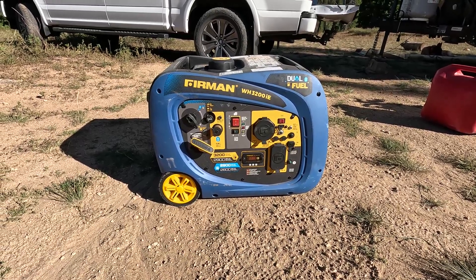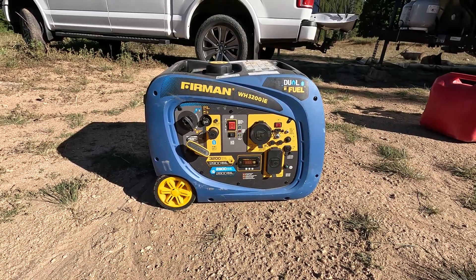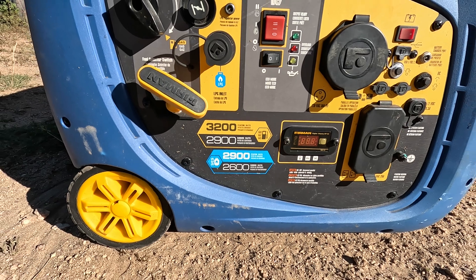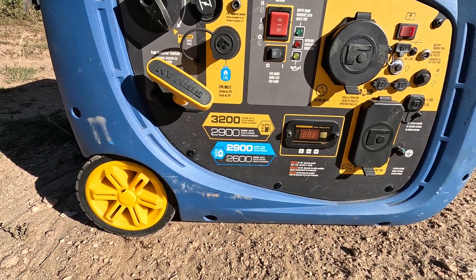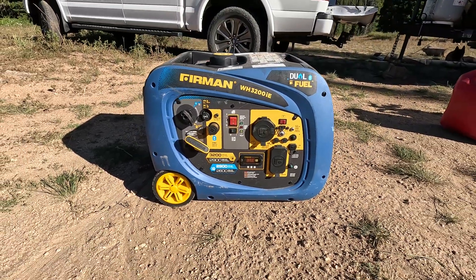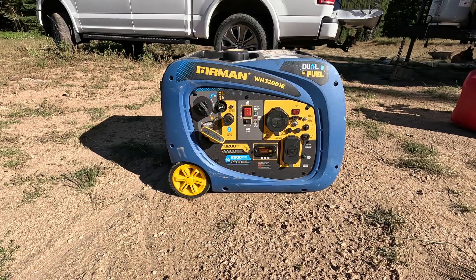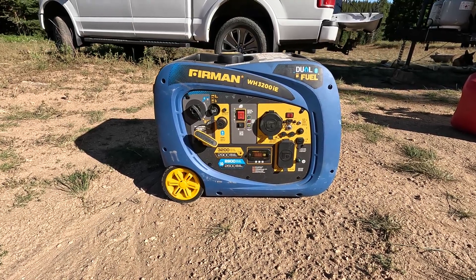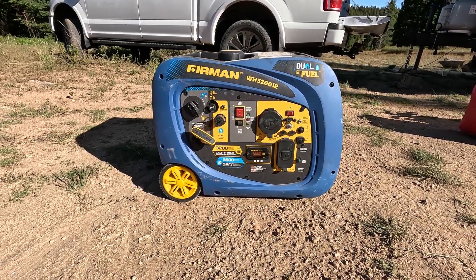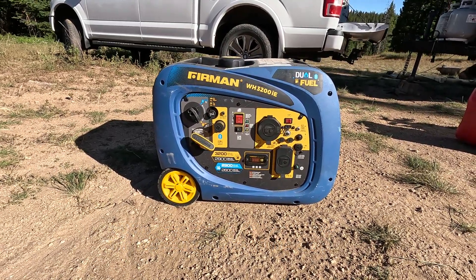I have this FIRMAN WH3200iE dual fuel inverter generator. At sea level, this generator is rated at 3,200 watts surge on gasoline, 2,900 watts running on gasoline, and then 2,900 watts surge and 2,600 on propane. We're going to do tests here today at 10,000 feet. Generators normally lose 4% of their rated output for every 1,000 feet of gain in altitude. So in theory, this machine will only put out 60% of its rated load, and we're going to test that today.